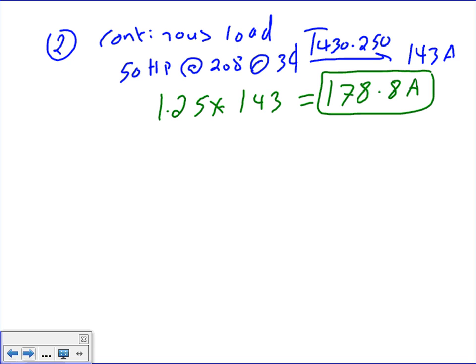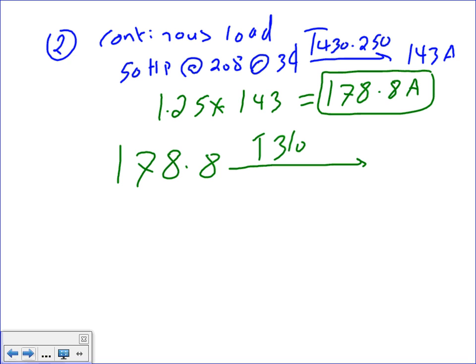Okay, then we're going to take this beautiful amp cable all the way to which table, Mr. Erbab? 310.16. Soon to change to 310.15 B something. Okay, table 310.16 under which column and why? 75. It's more, and also it's higher than 100 amp, and also it's a motor.